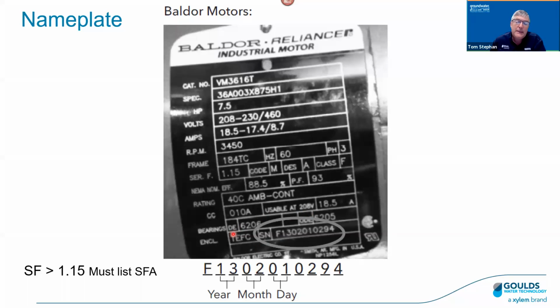You've got some bearing information. DE is the drive end bearing, and ODE is the opposite drive end bearing. It's a TEFC motor, totally enclosed fan cooled, and there's a serial number. The serial number is a unique number, but oftentimes that's where your date code is buried. We need to know how to read that, because all motor manufacturers use a different system. Baldor uses this system here: the 13 is the year, the 02 is the month, and the 01 is the day. So that's how you decipher the date code, at least with a Baldor motor.